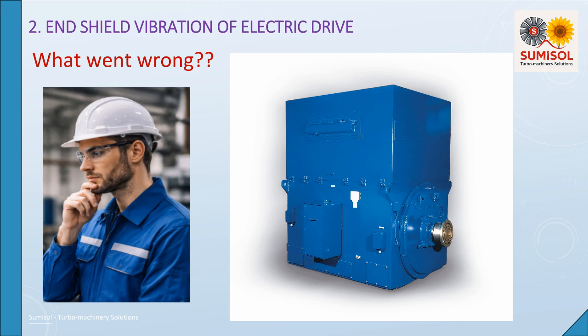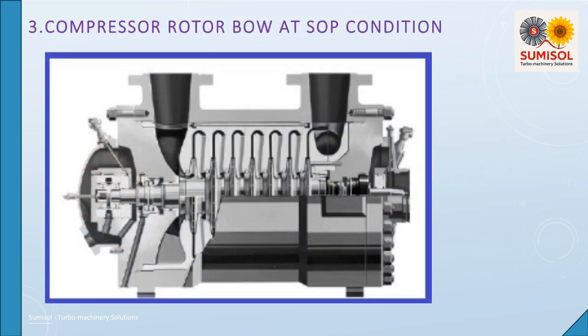The third case is related to centrifugal compressor transient vibration. After 8 hours of pressurized shutdown, the centrifugal compressor could not pass the first bending critical speed during startup. The compressor tripped on high shaft vibration. The rotor had passed the MRT, string test, and at site a 96 hour endurance test. Startup engineers and operations started thinking about implementing a soft start.